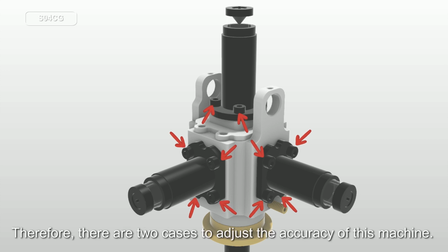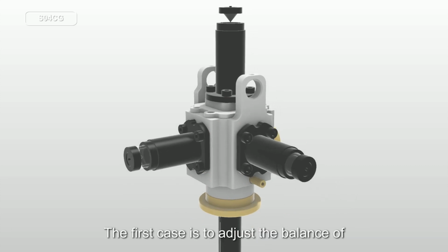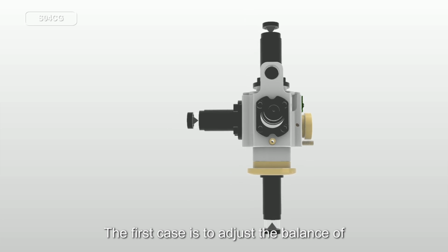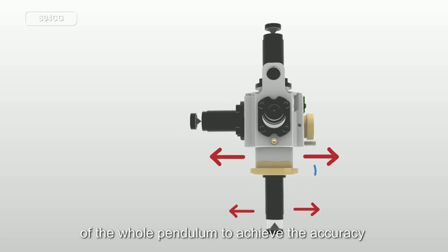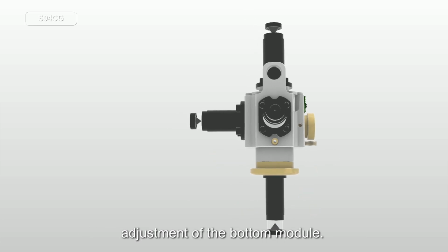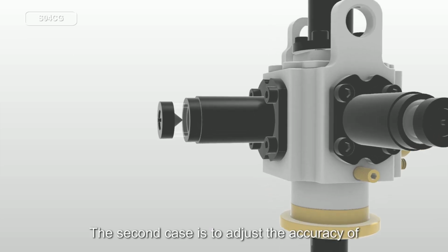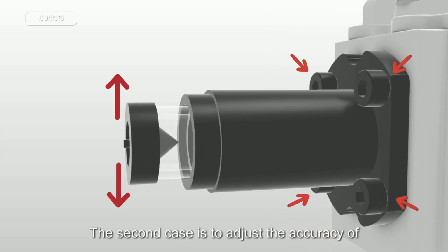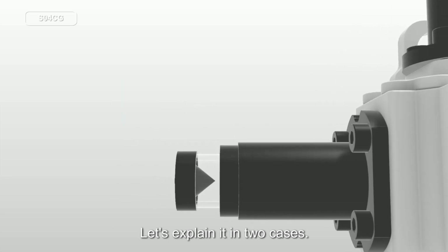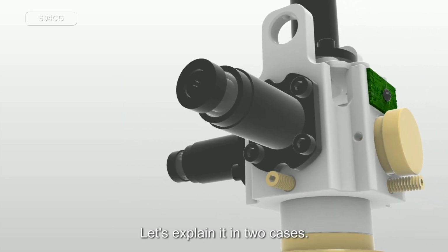Therefore, there are two cases to adjust the accuracy of this machine. The first case is to adjust the balance of the whole pendulum to achieve the accuracy adjustment of the bottom model. The second case is to adjust the accuracy of other individual laser models separately. Let's explain it in two cases.